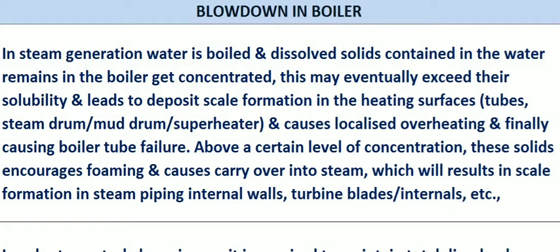In a boiler, water is continuously getting heated up and steam generation is happening. Due to that, the dissolved solids in the water will remain as such in the water, and the water will evaporate to form steam. So automatically the concentration of dissolved solids in the water will get increased. In certain stages they exceed their solubility, and there is scale formation on the heating surfaces — the boiler tubes, water wall tubes, superheater tubes, and the steam drums.